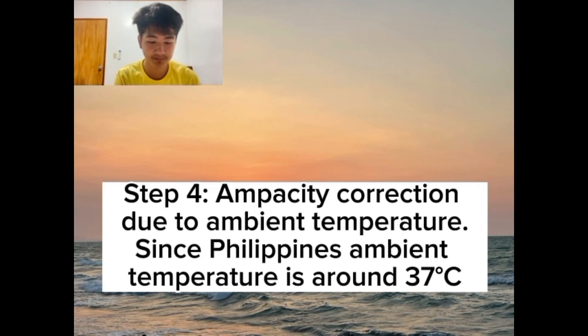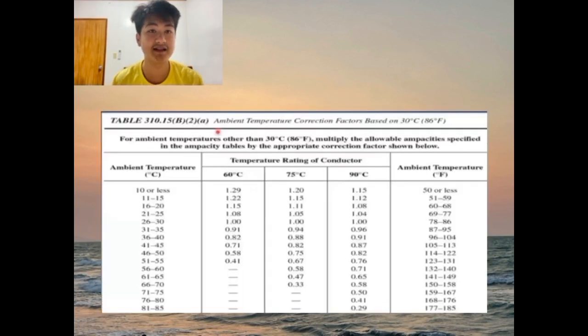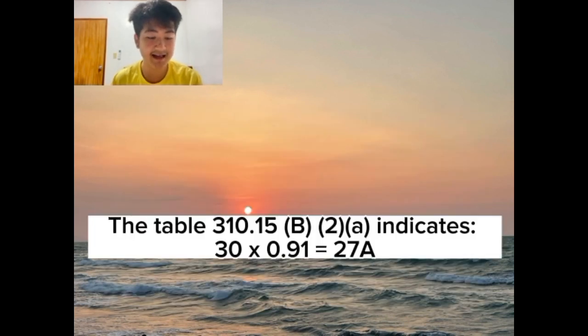So step 4. Ampacity correction due to ambient temperature. Since the Philippines' ambient temperature is around 37 degrees Celsius, tingnan natin sa table kung saan papasok si 37 degrees Celsius. Kung makikita nyo, pasok siya sa 36 to 40. Ang katapat naman ni 36 to 40 is si 0.91. Kaya imumultiply natin ang value natin sa 0.91 at ang magiging sagot niya is 27 ampere.